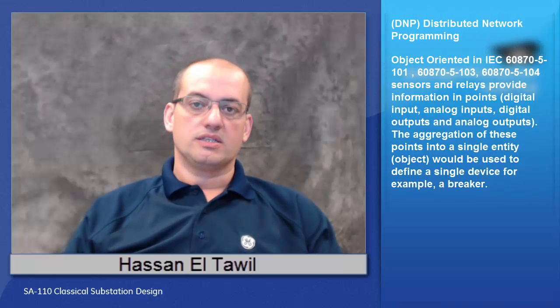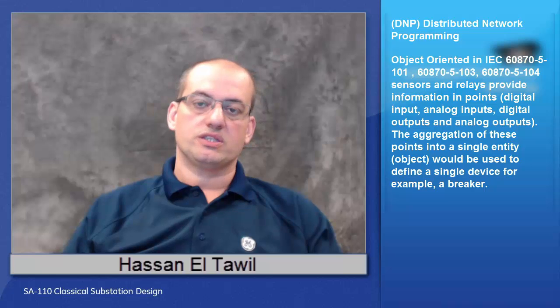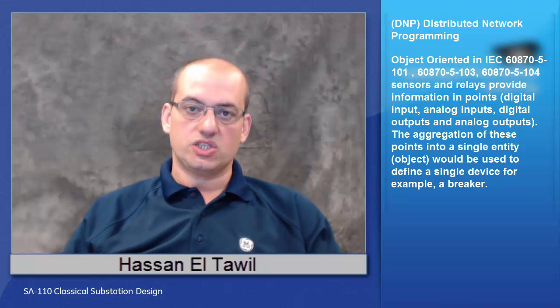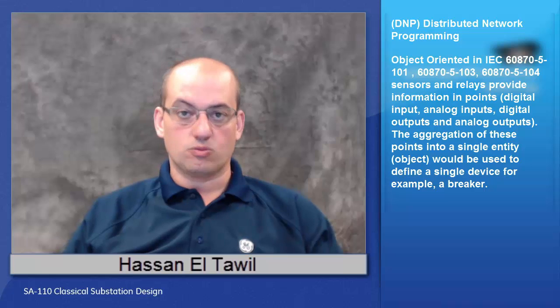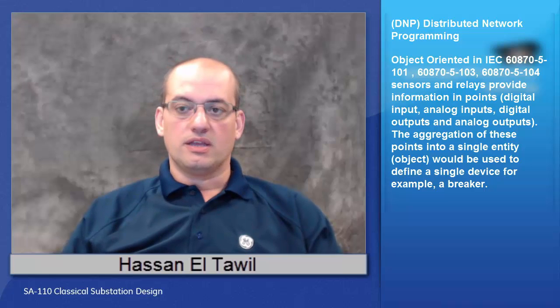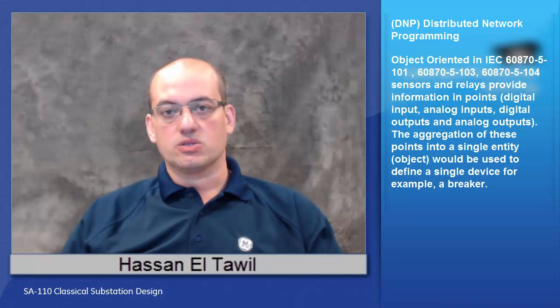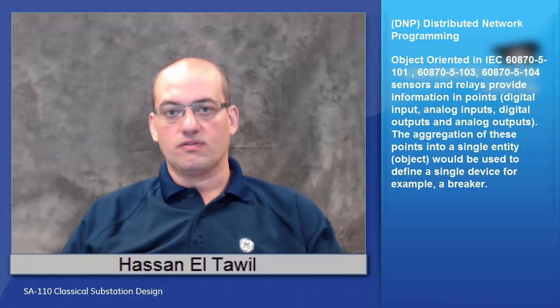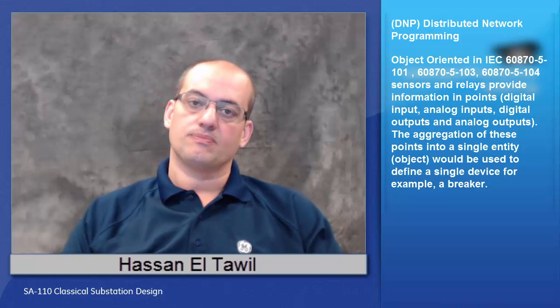Another common set of open protocols is IEC 60870-5-101, 103, and 104. These open protocols started the object-oriented era, where instead of dealing with a piece of information generated by a sensor as just a digital input, digital output, analog input, analog output, or counter, the information was bundled together.